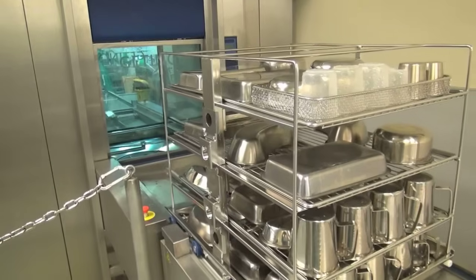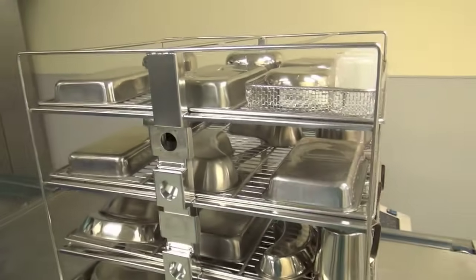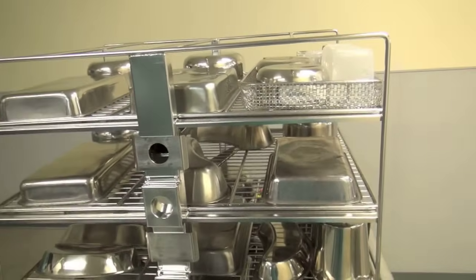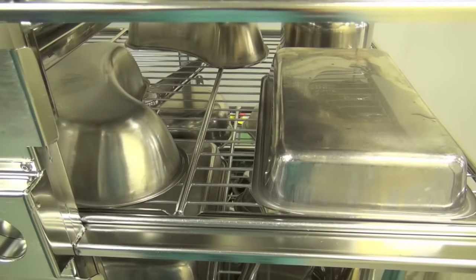About 45 minutes later, the Turbo is done. It's all automatic. We have an air glide system that comes by, picks up that tray and deposits it on a carousel. And then the staff takes it out and redistributes it. The instruments themselves are clean and well lubricated and are safe to handle.